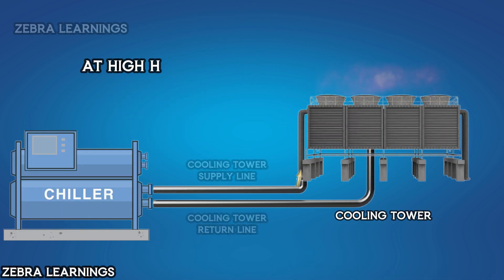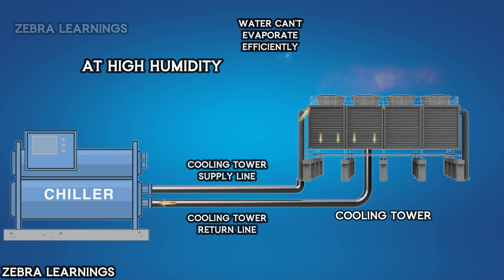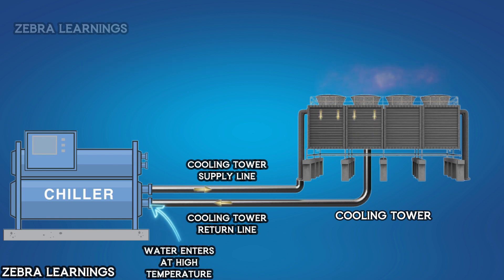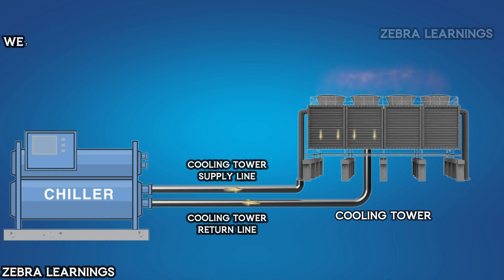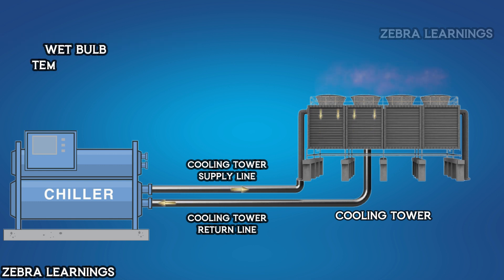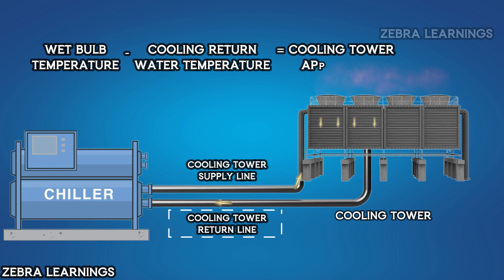However, when the humidity is high, the water cannot evaporate efficiently and the water temperature does not decrease much. As a result, the water returns to the chiller at a higher temperature, which reduces the chiller's efficiency. When the wet bulb temperature exceeds 25°C, the cooling tower's performance starts to decrease. The difference between the wet bulb temperature and the cooling tower's return water temperature is the cooling tower's approach value.